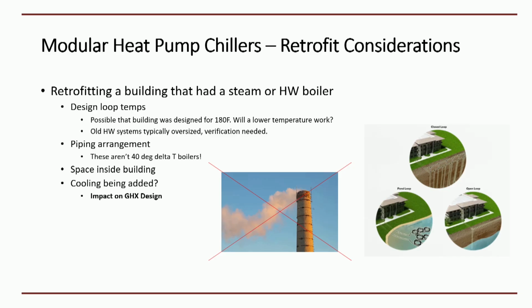A lot of old hot water systems were oversized. I can't tell you time and time again, we're asked for a selection on one of these types of systems, and people are simply trying to mimic maybe the 2 big boilers that were down in the boiler room before. Well, it's really good to look into that, because maybe one of those was redundant. Maybe you really don't need that much capacity, because that might equate to 10 modules of one of these heat pumps rather than 6. So it's really good to do your homework, understand what your building needs and what's going to keep it ticking, and not just assume that what was there was right and proper.